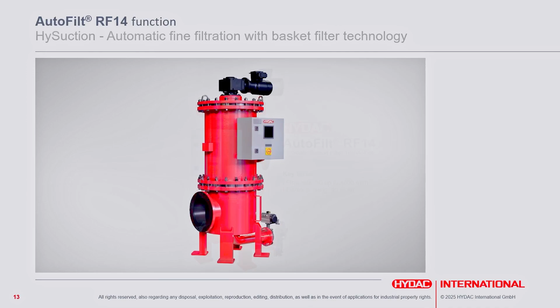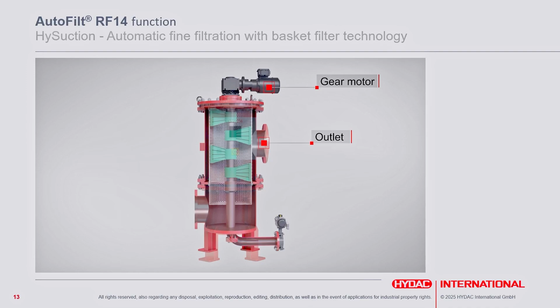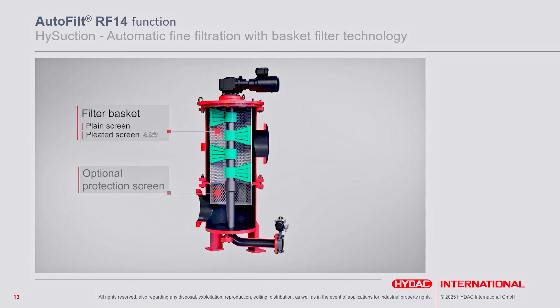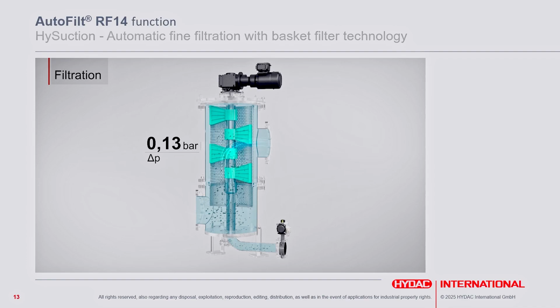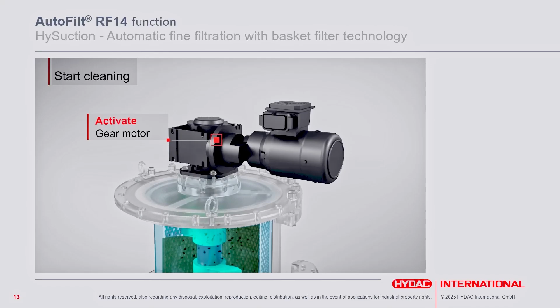As I told you, inlet at the bottom left, outlet at the top right, backflushing line with a backflushing valve at the bottom right. We have the gear motor and the flushing mask with its nozzles in the middle and one filter basket. The water comes in with particles on the bottom left and leaves the filter on the top right without particles. While doing so, the dP, the pressure from inlet to outlet, increases until triggering dP. The control starts the backflushing, the gear motor turns, the backflushing valve opens, and the basket gets cleaned with very high velocity, very high turbulence. And because of this high velocity and turbulence, we are able to filter much finer compared to RF3. Yeah?